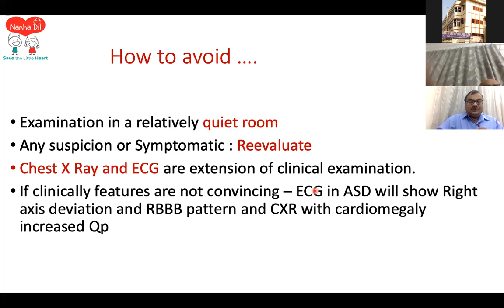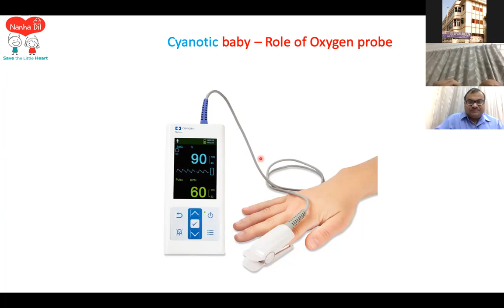Just I want to touch on cyanosis and the importance of pulse oximeter. Nowadays, I believe sir can confirm, checking of oxygen saturation is now coming into the curriculum. Our bare eye cannot detect the oxygen level in the range of 80 to 85 to 94. This range is difficult to pick up. That requires a good oxygen saturation probe with a good pleth. So if we are getting a good curve, then only we should consider that as a correct saturation.